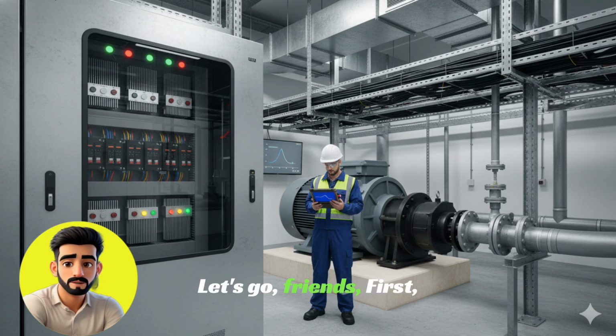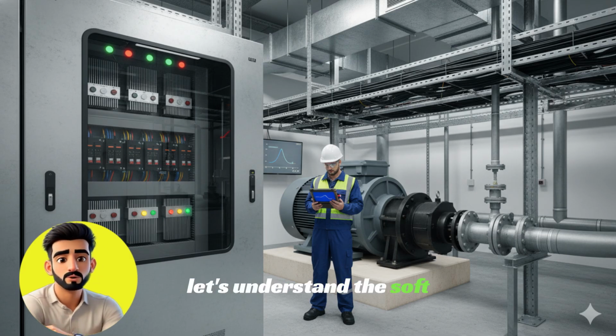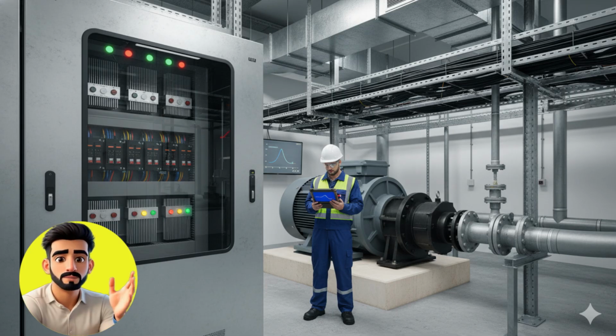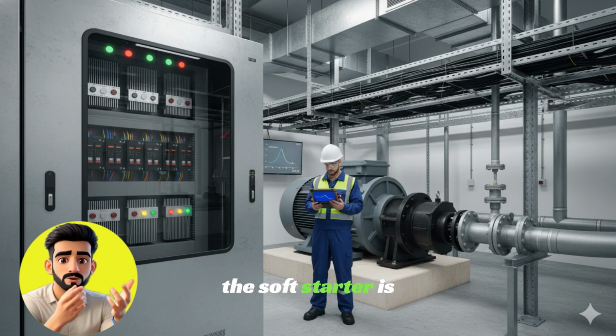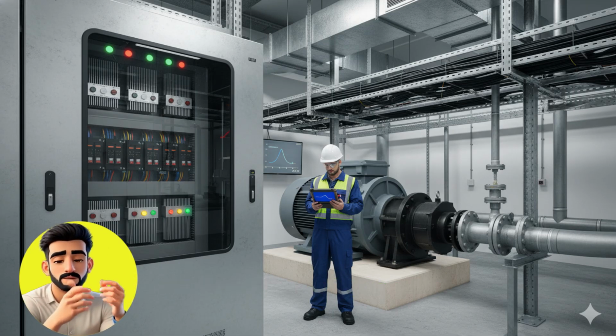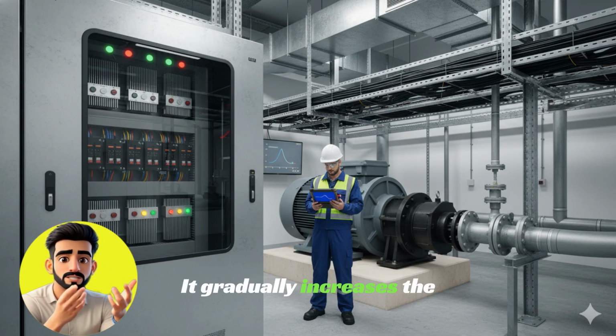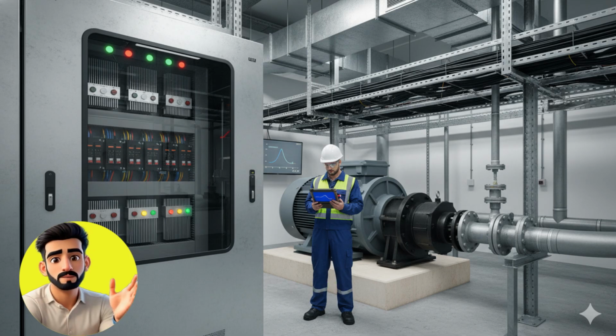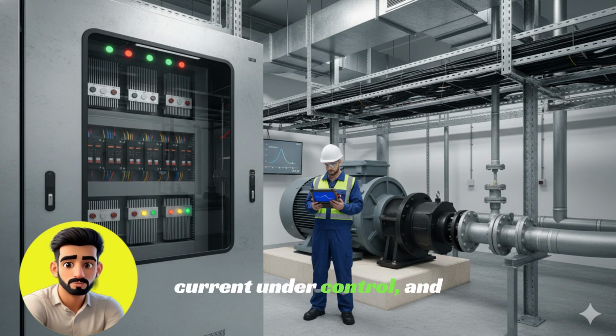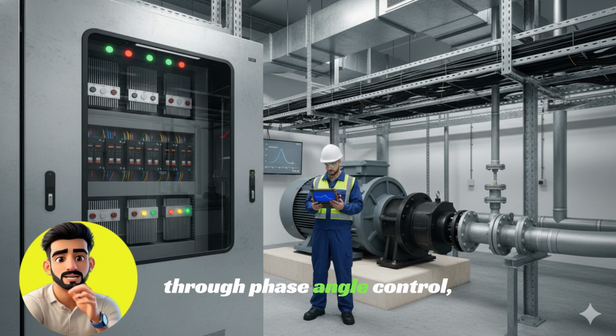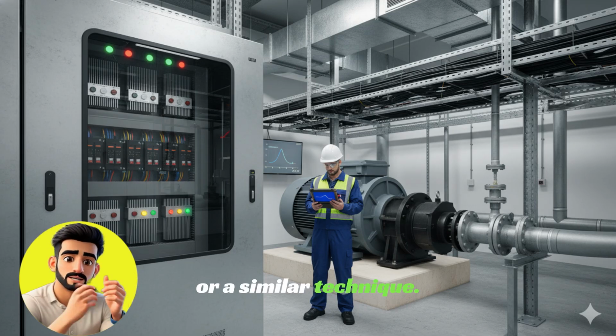Let's go, friends. First, let's understand the soft starter with full respect, because in many applications, the soft starter is the best solution. The basic principle of a soft starter is simple. It gradually increases the voltage when starting the motor. This keeps the starting current under control, and the starting torque also becomes smooth. This is usually done through phase angle control or a similar technique.